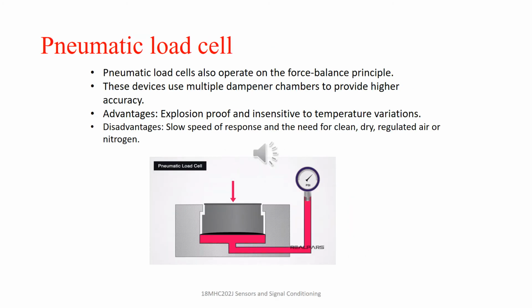Next is the pneumatic type. These also operate on the force balance principle. This uses multiple damper chambers to provide higher accuracy than the hydraulic load cells. This type is mainly used to measure relatively small weights in industries. The advantages of this type of load cell include being explosion proof and insensitive to temperature variations. Also, they contain no fluids that might contaminate the process if the diaphragm ruptures. Disadvantages include relatively slow speed of response and the need for clean, dry and regulated air or nitrogen.